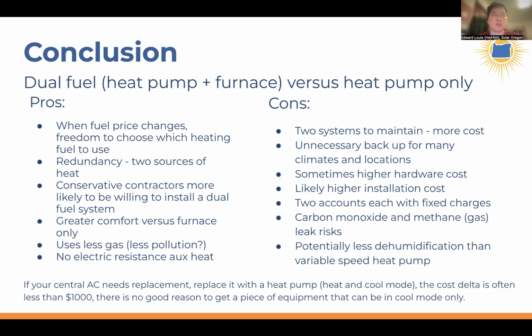If you have a dual fuel system, during defrost the thermostat will actually turn on the gas furnace so that you have heat during the defrost period, so you won't need electric resistance auxiliary heat. Not that you need auxiliary resistance heat in a straight heat pump system. If you're okay with 5-10 minutes every hour or 2 or 3 hours of having either no heat or slightly cool air coming out of your vents during the defrost period, then you really don't need electric resistance auxiliary heat.